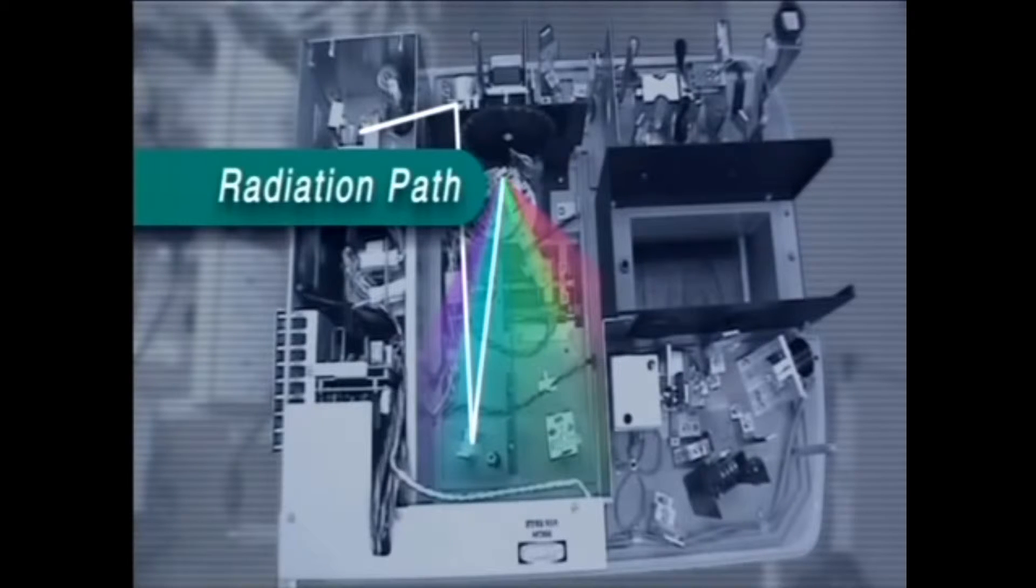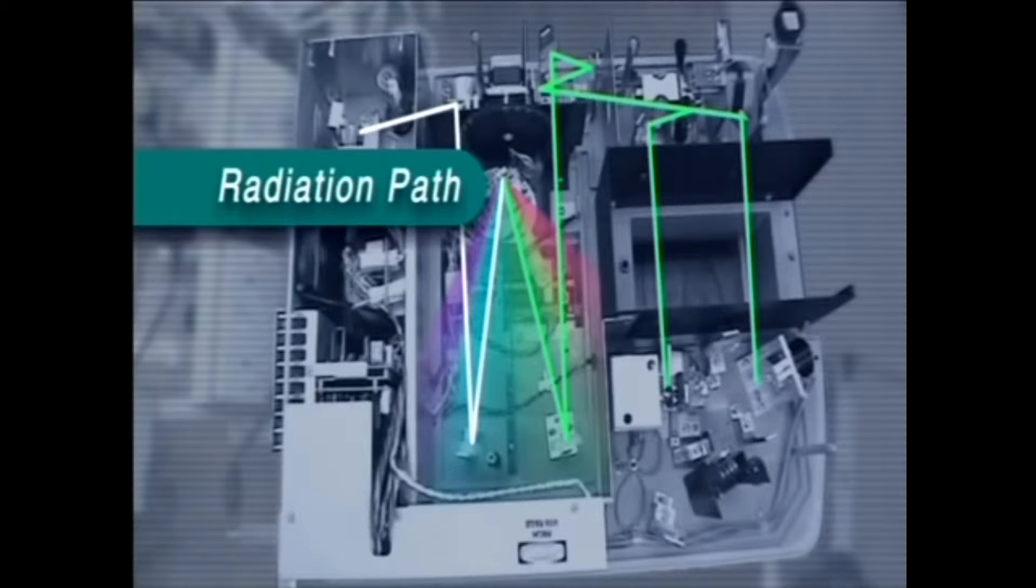A single wavelength passes into the modulator which consists of a rotor with mirrors on it. This chops the light into two beams. One beam passes through the sample cell while the other passes through the reference cell. So the instrument is referred to as a double beam instrument.